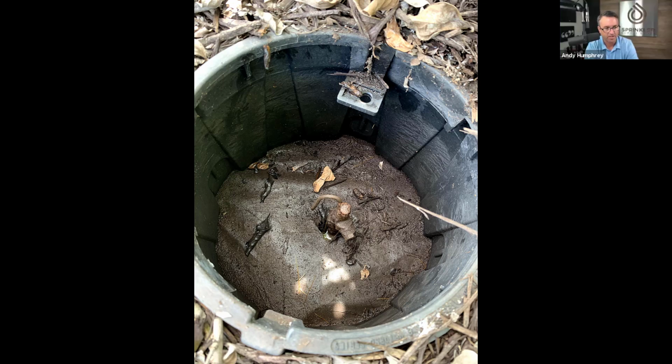Yeah, and it looks like that soil is nice and wet, so that is aiding in that nice low reading. Yeah, right. Definitely. Absolutely. It's wet, and then this is the double-edged sword for some of the sandier soils or just pure sand soil in Florida and other parts: sandy soil is really easy to drive a rod in, whereas in the county that I'm in, it can be quite rocky soil.